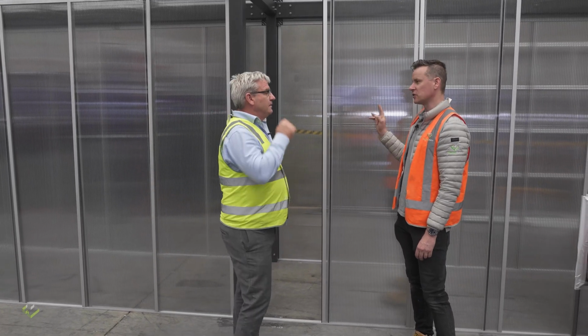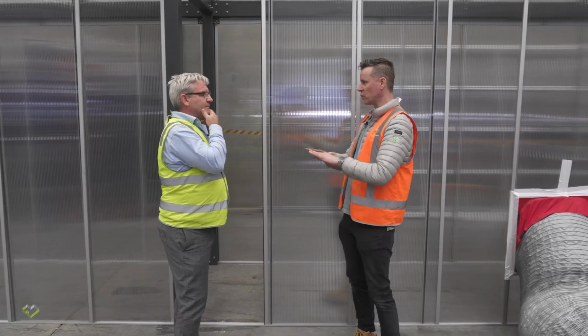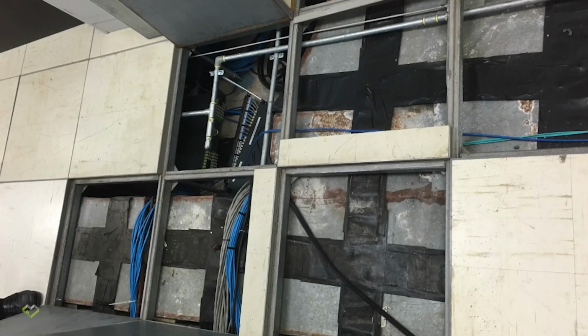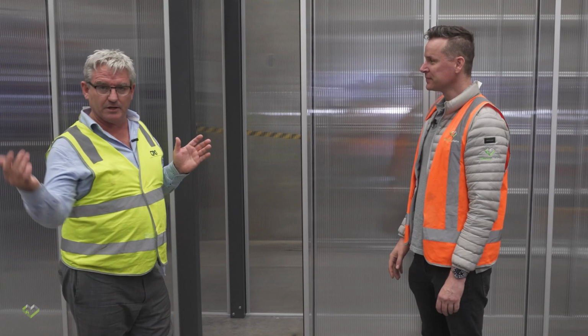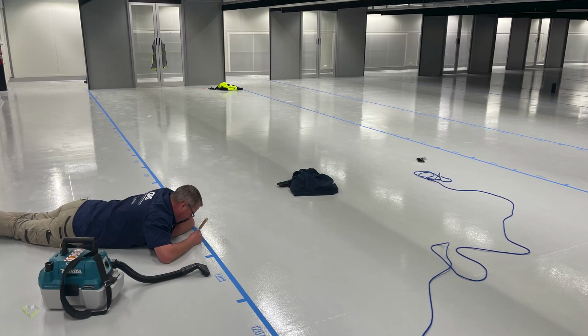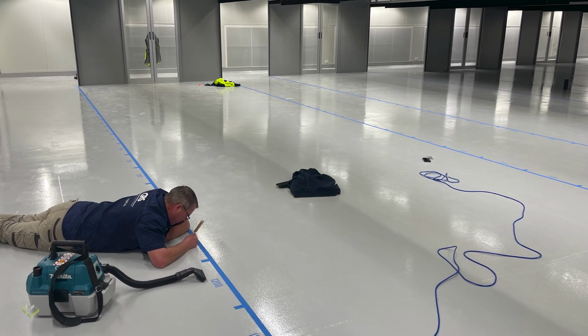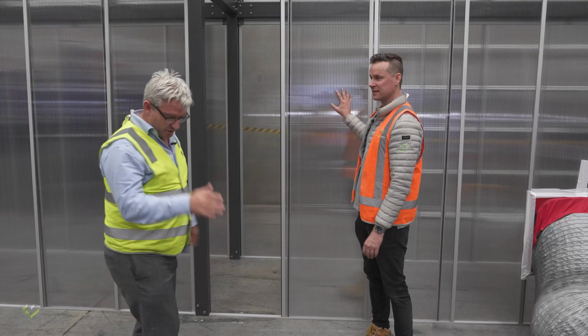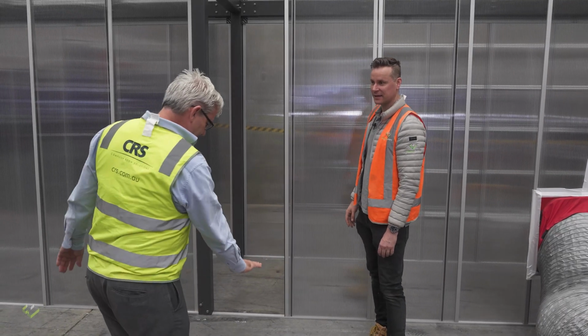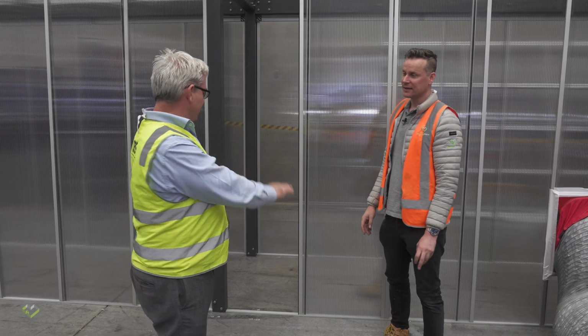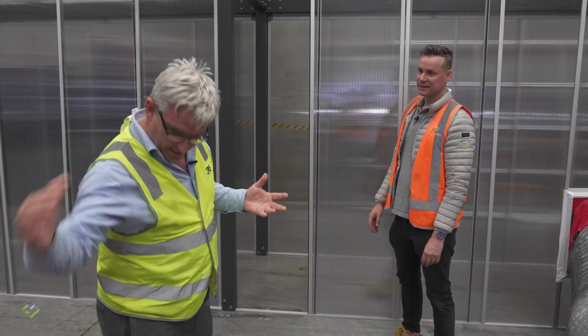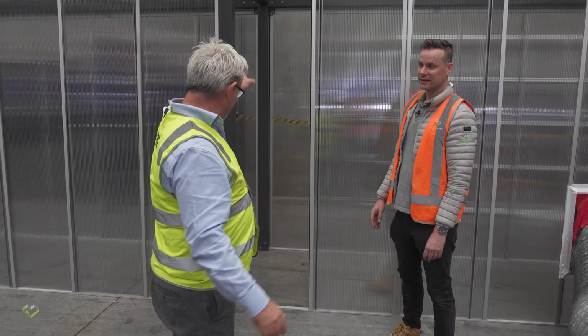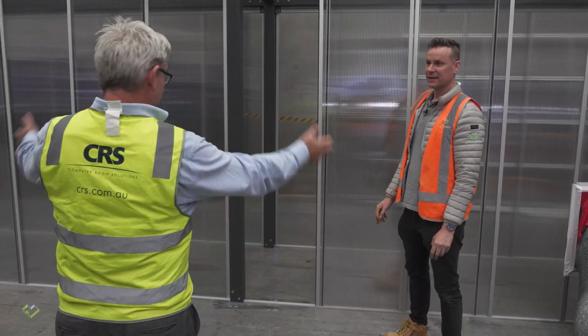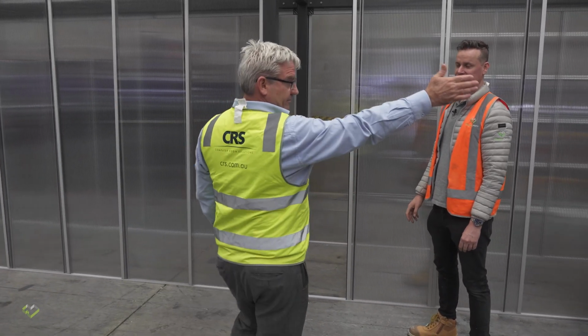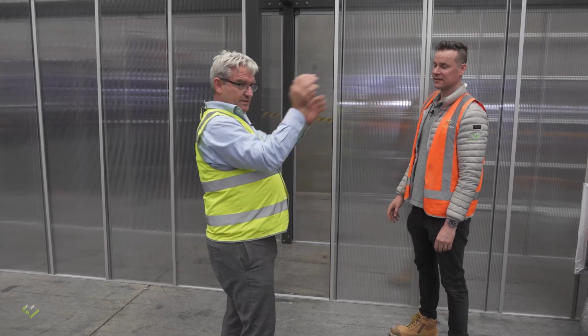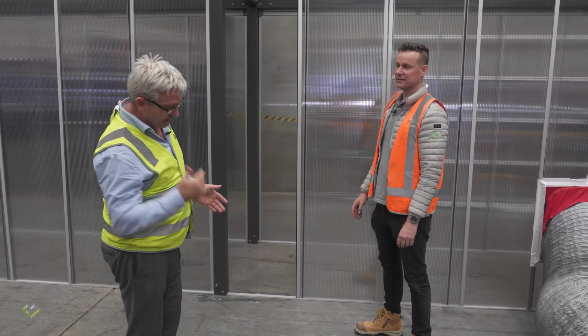Do you normally put these onto false floor systems, or is false floor gone now? False floor is a thing of the past, we'll say. Now you're blowing the cold air into the data hall on a concrete slab, and then you're getting your hot air out. But no, raised floor, once upon a time you would have grills here on a raised floor. You'd have a 600 floor or a metre high floor, 1.2, whatever it might be. Blowing your cold air under the floor, up here through the grills, through your racks into the hot aisle. Now you're just flooding this area with cold air. You'll generally have your fan walls at the end, it'll blow down here and the racks will pick it up on the way through.